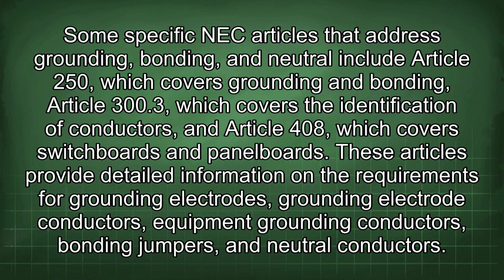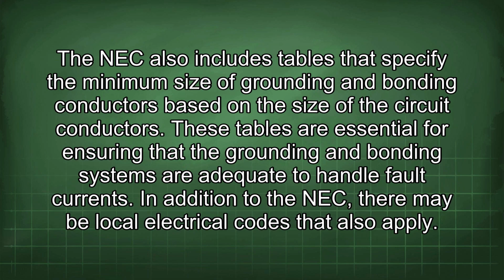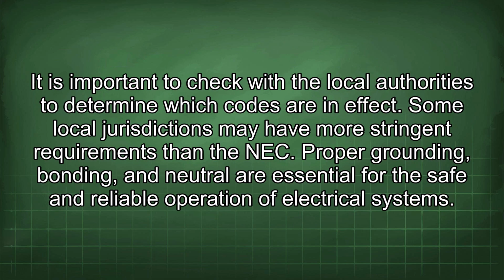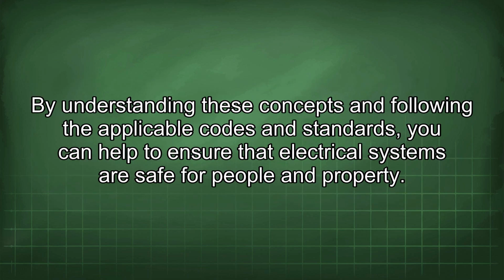These articles provide detailed information on the requirements for grounding electrodes, grounding electrode conductors, equipment grounding conductors, bonding jumpers, and neutral conductors. The NEC also includes tables that specify the minimum size of grounding and bonding conductors based on the size of the circuit conductors. These tables are essential for ensuring that the grounding and bonding systems are adequate to handle fault currents. In addition to the NEC, there may be local electrical codes that also apply. It is important to check with the local authorities to determine which codes are in effect. Some local jurisdictions may have more stringent requirements than the NEC. Proper grounding, bonding, and neutral are essential for the safe and reliable operation of electrical systems. By understanding these concepts and following the applicable codes and standards, you can help to ensure that electrical systems are safe for people and property.